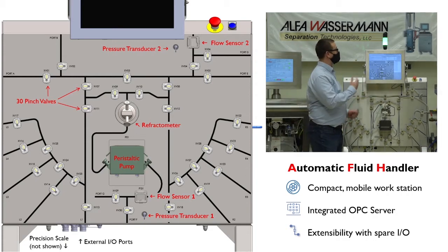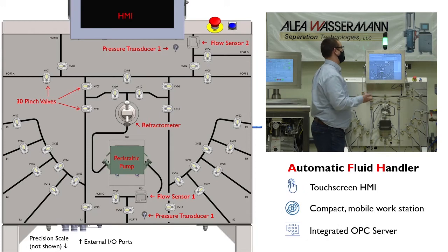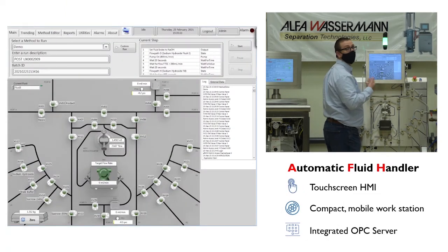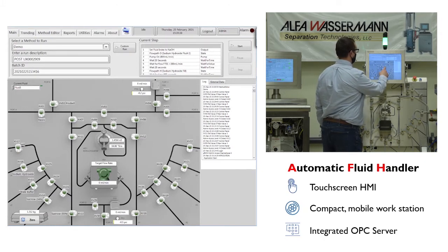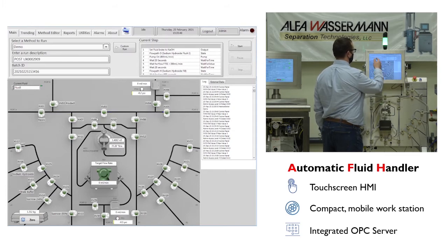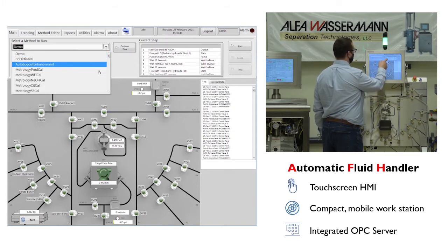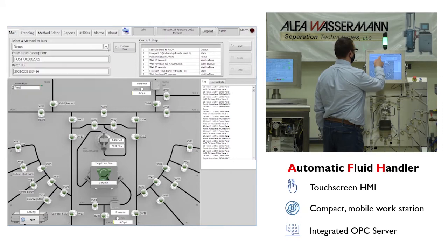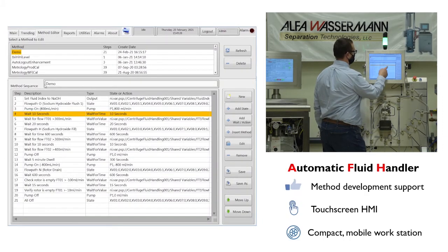All this instrumentation is displayed and controlled with a touchscreen HMI computer where an operator can see real-time values from all the sensors and instrumentation that I just mentioned. In addition, this is where an operator can manually control pinch valves and flow rates. But really, this system is designed to operate automatically based on a method, which is usually written by a supervisor or an engineer. This is done over here on the method editor tab.